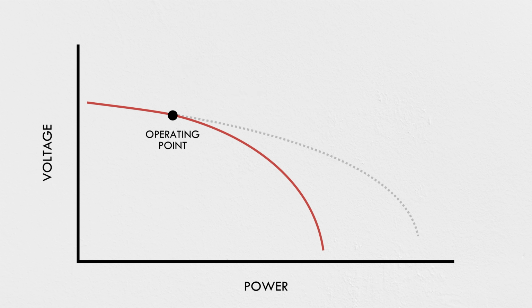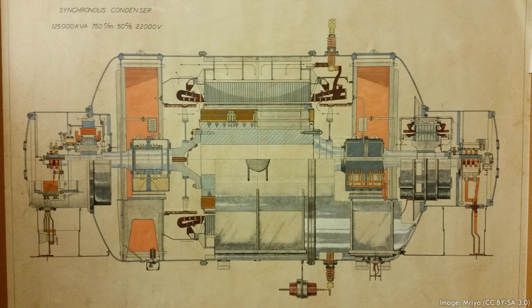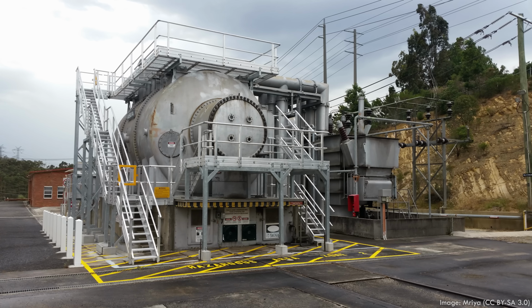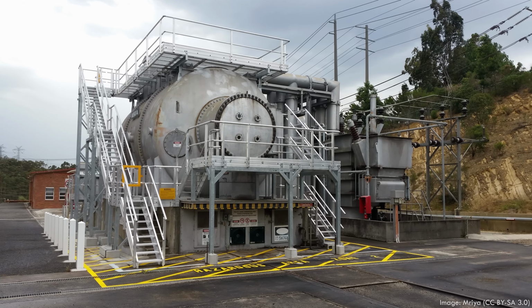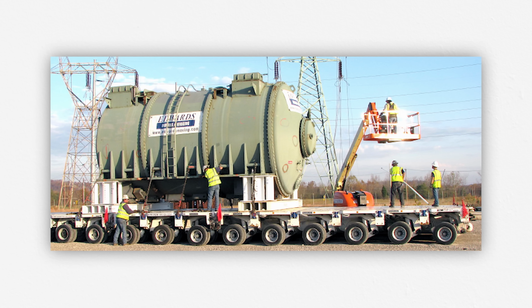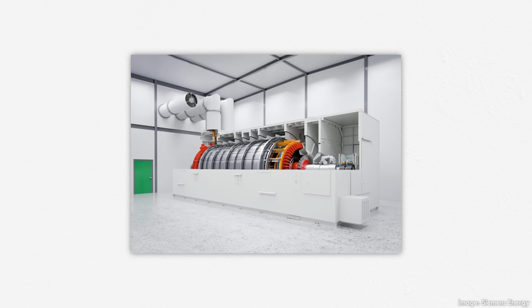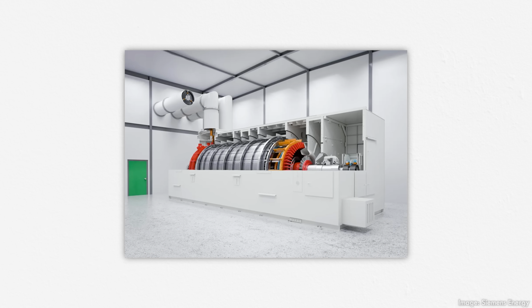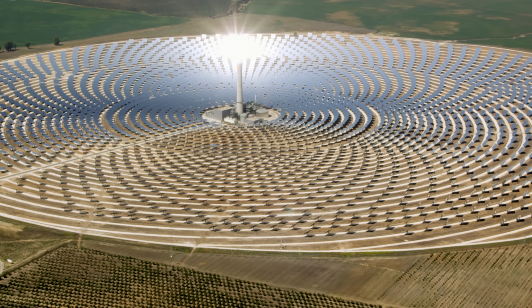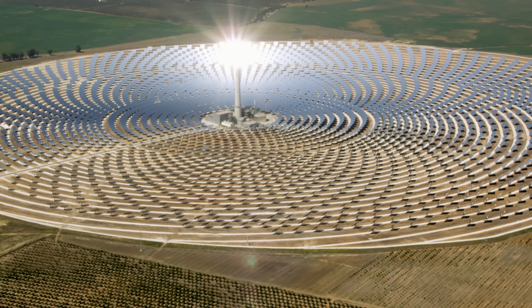So we use several ways to supply reactive power to provide voltage support and shift the curve back up. Power plants can adjust their operating parameters to supply reactive power, but transmission lines have their own inductance that consumes the reactive power as it travels through. So it's usually more efficient to address the problem on the load side, and there are several types of infrastructure that make this possible. Synchronous condensers are big motors that aren't actually attached to anything. Instead of converting electrical power to mechanical power, they basically spin freely. But with some clever circuitry, they can generate or absorb reactive power from the grid. They can also help stabilize fluctuations in the grid with the inertia of their heavy rotating mass, something that's becoming increasingly important as we transition more to renewable sources that use inverters to connect to the network.